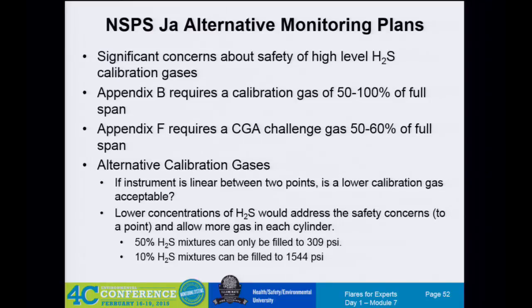But one of the things is it gets into the issue of linearity in the monitoring device. We're already just doing 2-point calibration and assuming linearity. We have that point within the 0 to 20% and then the 50 to 100%, and that's how you're doing your daily calibration drift. So we're going to assume linearity between those 2 points. Why does that higher point need to be from 50 to 100%? If it's linear, it's linear. So instead of using 50%, why can't we go down to maybe 10% or 1%?